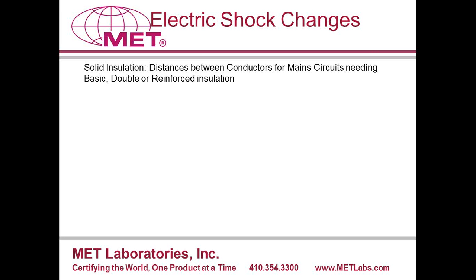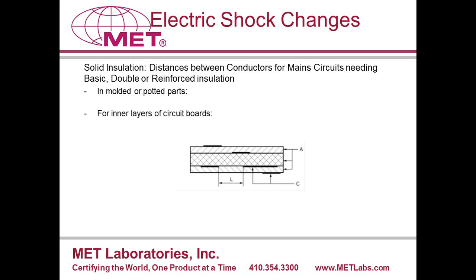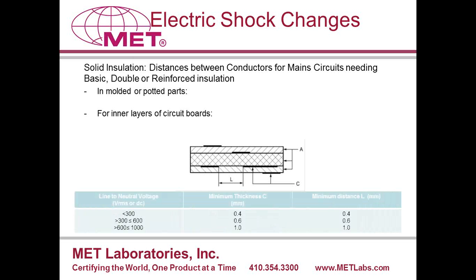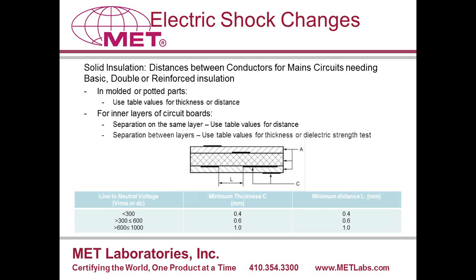Another change in the standard is the inclusion of spacings in solid insulation, specifically molded and potted parts, multi-layer circuit boards, and thin film. The standard addresses distance between traces within a layer, L, and distance between layers, C. For products under 300 volts, there's a separation requirement of 0.4 millimeters for both L and C, whether the insulation is basic, double, or reinforced. Between layers of circuit boards, there's also the option of doing a dielectric strength test instead of a measurement.